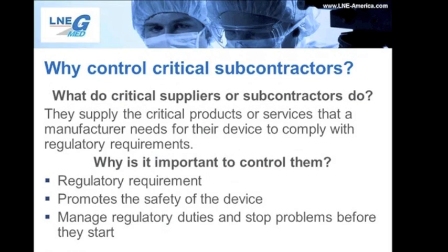Given the important jobs that the critical subcontractors do, it should be clear why a manufacturer would need to control them. First, it's a regulatory requirement. The directives say you have to, so you have to. Second, control of critical subcontractors helps to promote the safety of the device.